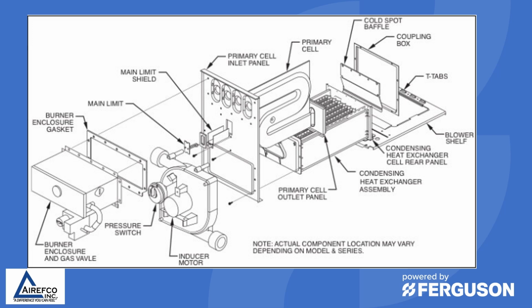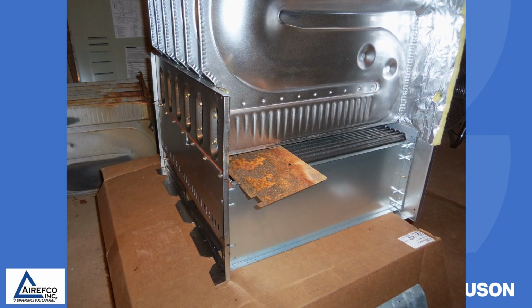So always when you get a kit to replace the heat exchanger, the primary or secondary, make sure that you have a document that shows you the complete breakdown of all the parts that need to be there to make the furnace operate correctly. A very common call that we get during the winter in tech support on Carrier and Bryant 90% furnaces of older vintage is the missing rear air baffle.